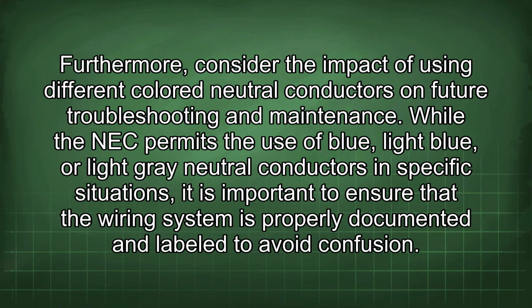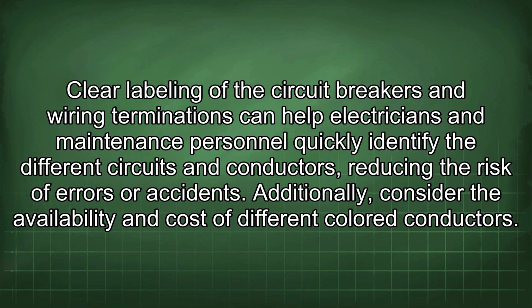Furthermore, consider the impact of using different colored neutral conductors on future troubleshooting and maintenance. While the NEC permits the use of blue, light blue, or light gray neutral conductors in specific situations, it is important to ensure that the wiring system is properly documented and labeled to avoid confusion. Clear labeling of the circuit breakers and wiring terminations can help electricians and maintenance personnel quickly identify the different circuits and conductors, reducing the risk of errors or accidents.